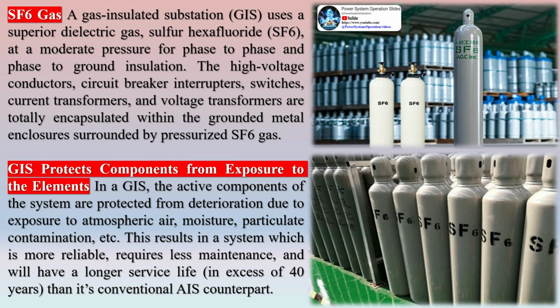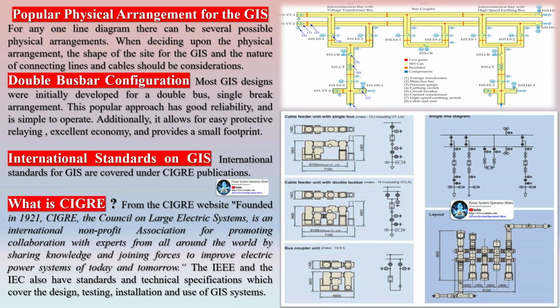The high-voltage conductors, circuit breaker interrupters, switches, current transformers, and voltage transformers are totally encapsulated within grounded metal enclosures surrounded by pressurized SF6 gas. In a GIS, the active components of the system are protected from deterioration due to exposure to atmospheric air, moisture, particulate contamination, etc. This results in a system which is more reliable, requires less maintenance, and will have a longer service life, in excess of 40 years, than its conventional AIS counterpart.